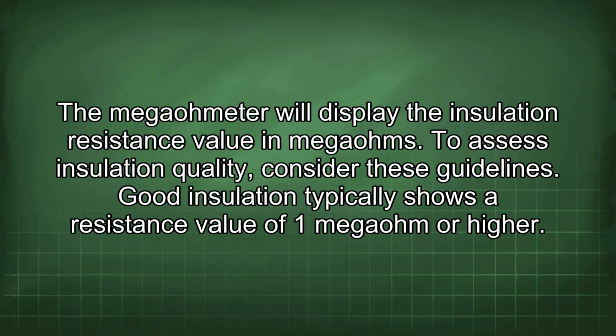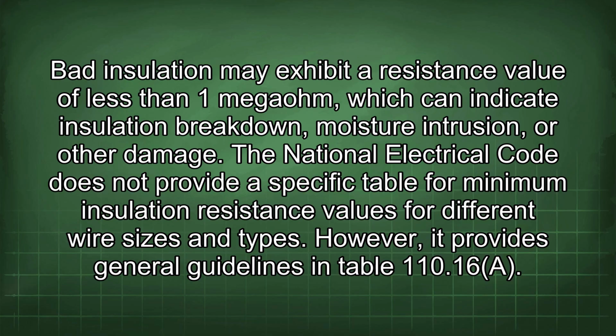To assess insulation quality, consider these guidelines. Good insulation typically shows a resistance value of 1 megaohm or higher. Bad insulation may exhibit a resistance value of less than 1 megaohm, which can indicate insulation breakdown, moisture intrusion, or other damage. The National Electrical Code does not provide a specific table for minimum insulation resistance values for different wire sizes and types. However, it provides general guidelines in Table 110.16(A).